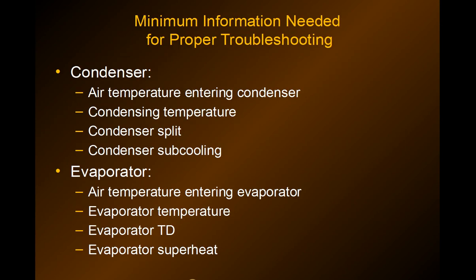The minimum information needed for proper troubleshooting is the air temperature entering the condenser, the condensing temperature, condenser split, and condenser subcooling. You'll find the rule-of-thumb values for the different types of systems on the cheat sheet.